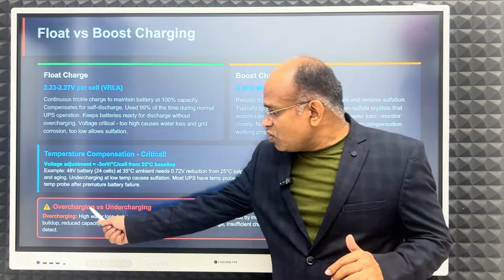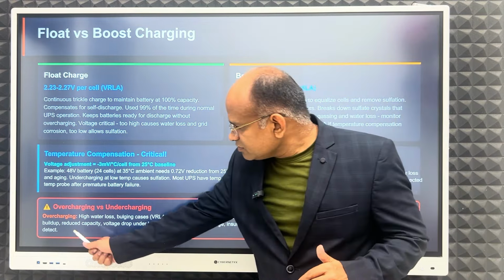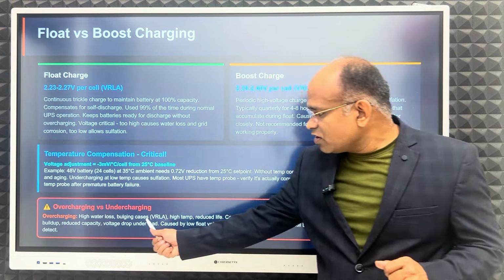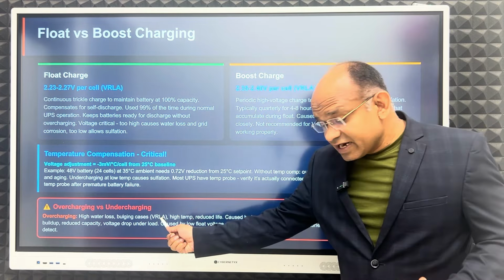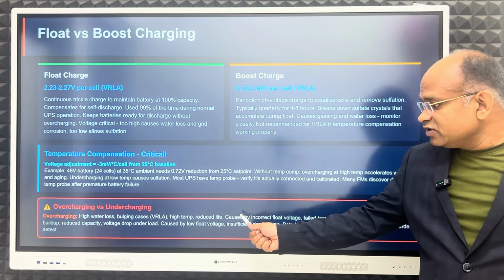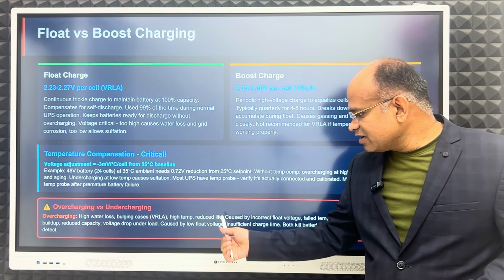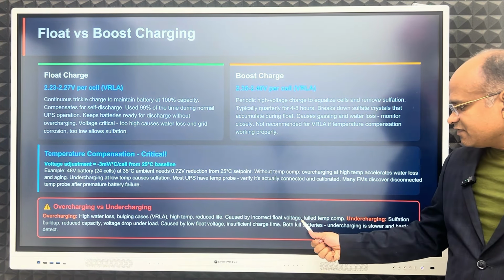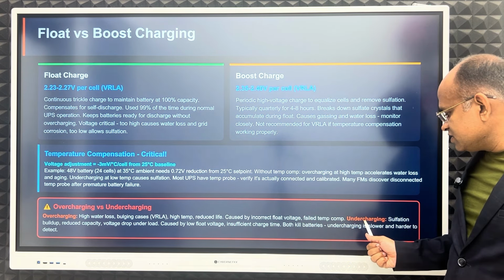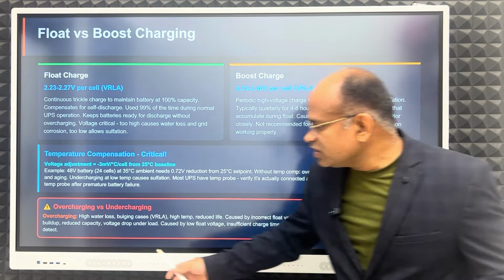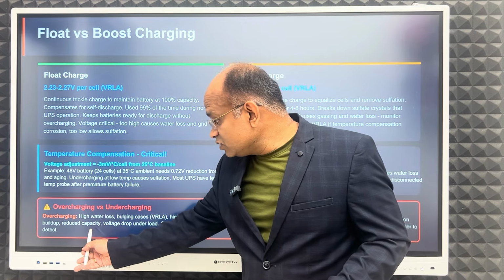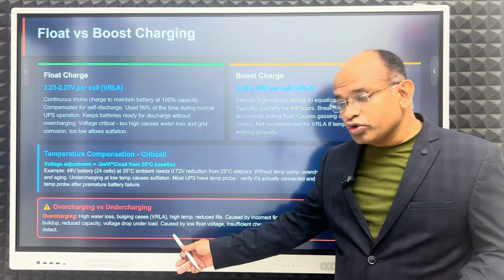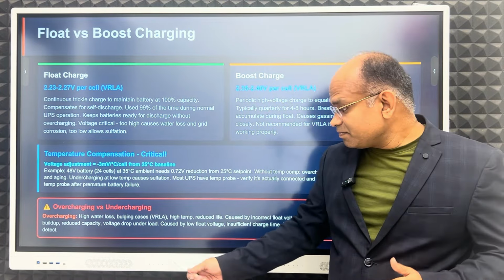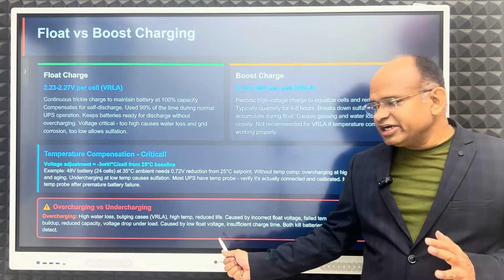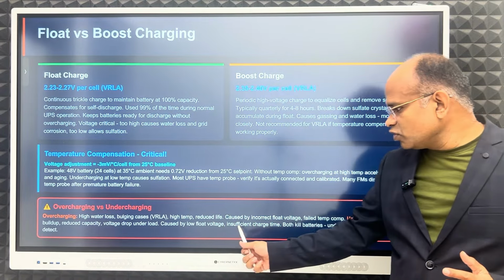Now, overcharging versus undercharging. Overcharging causes high water loss and bulging cases; it can bulge. In case of VRLA, high temperature reduces life. Obviously temperature is the killer of life, caused by incorrect float voltage or failed temperature compensation. Undercharging causes sulfation buildup, then reduced capacity, then voltage drop under load. Under load the voltage will drop. These are caused by low float voltage.